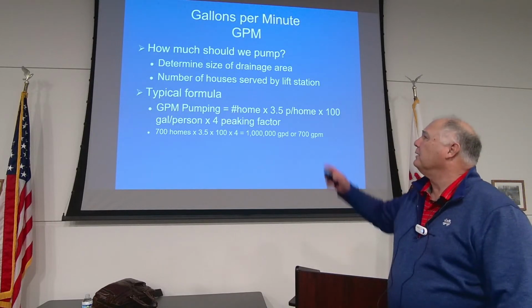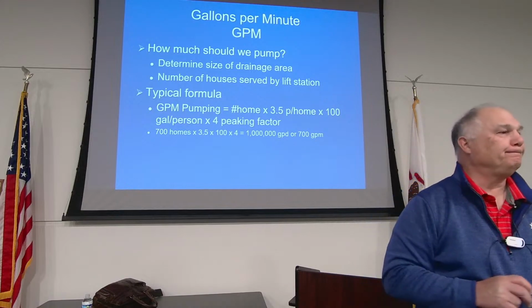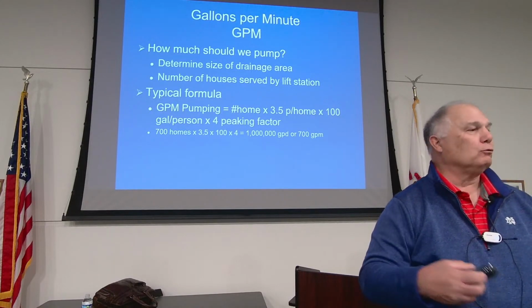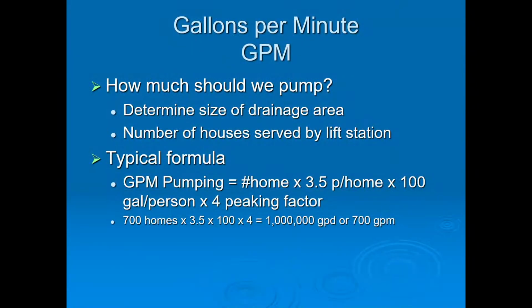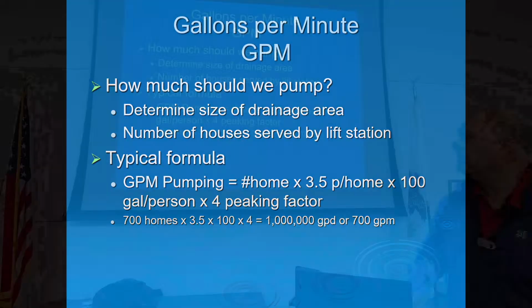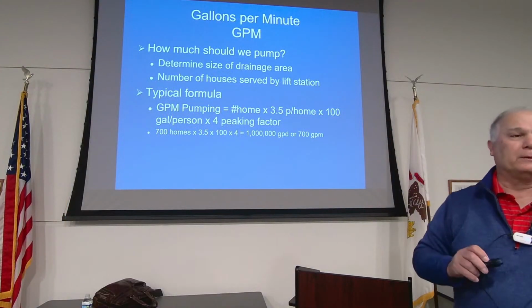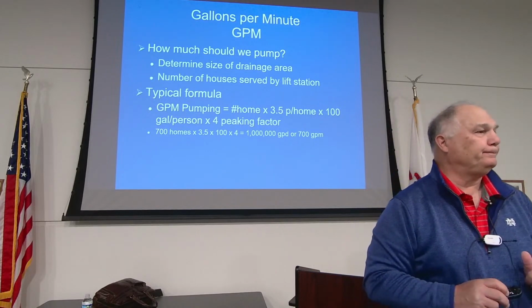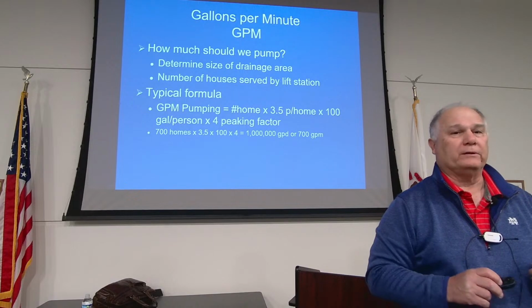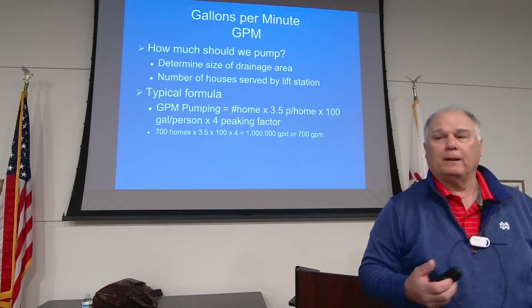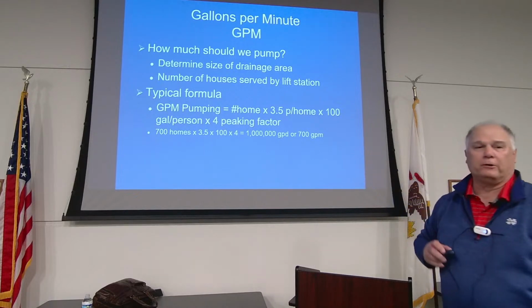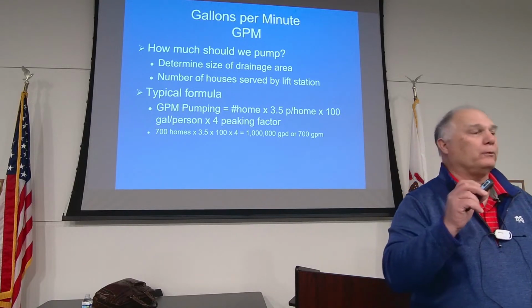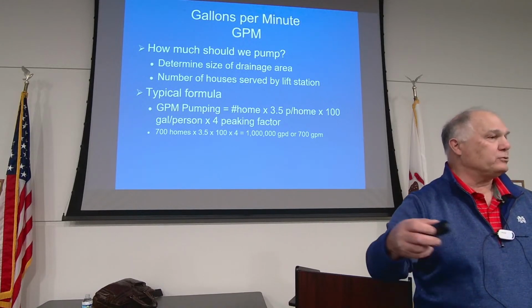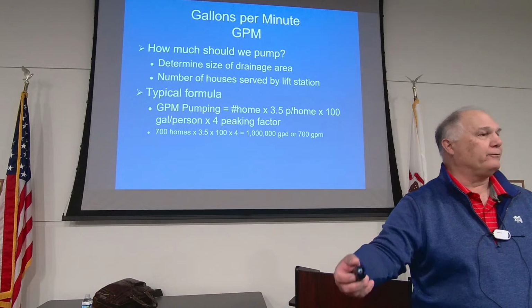So the first thing is how many gallons a minute do we need to pump? In the pump world, we have a rule of thumb. We've got to make sure that we have enough capacity for whatever we're going to pump to get the water out of the collection system, regardless of what the head's going to be. Therefore, we typically look at 1 GPM per home. For every home, we typically say we're going to have about 3.5 people in the home, 100 gallons per person per day, roughly. We take the number of homes that we're going to maintain times 3.5 times 100. It's going to give us a GPM for 24/7.